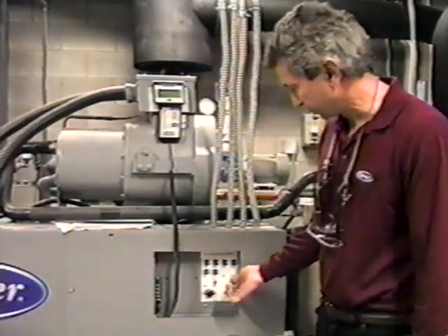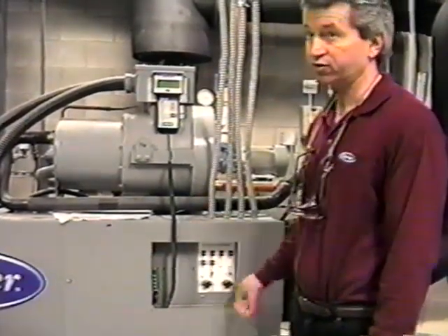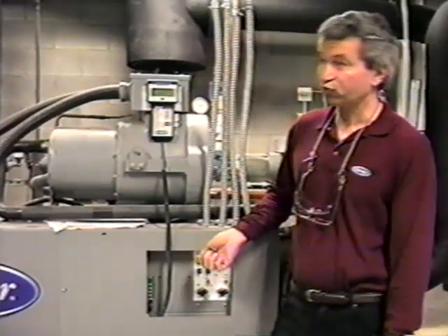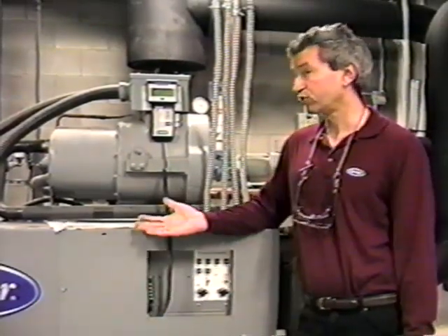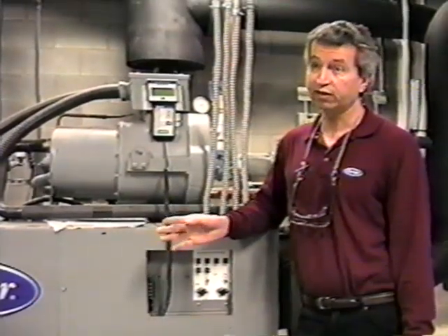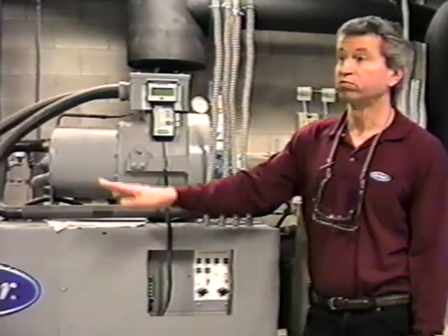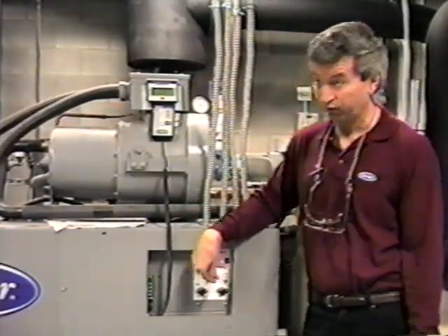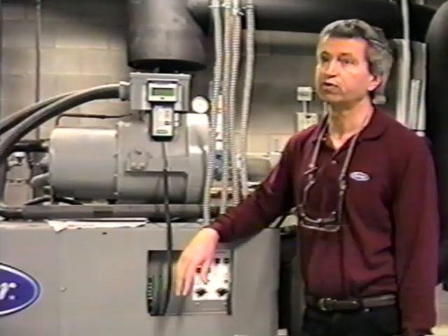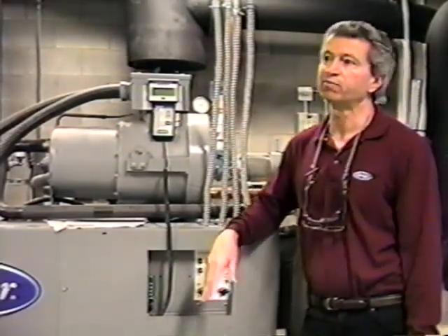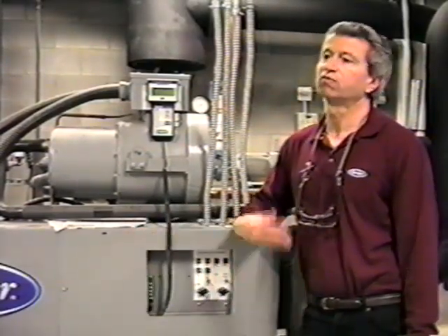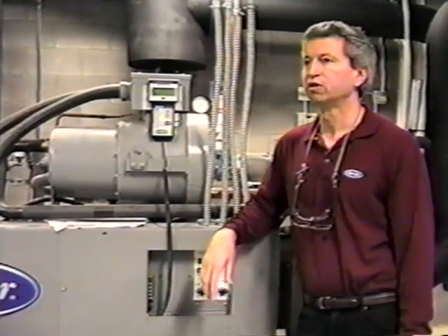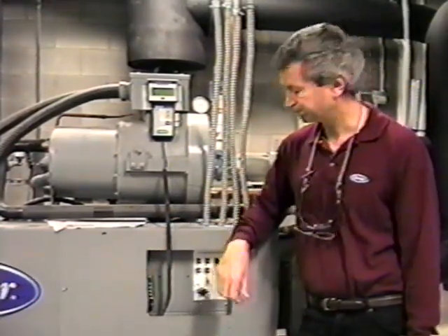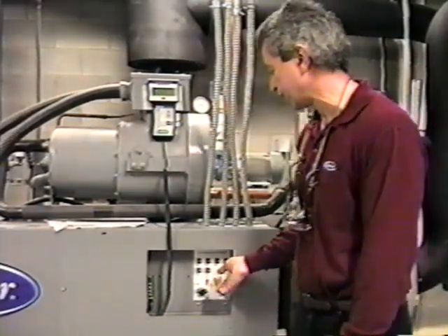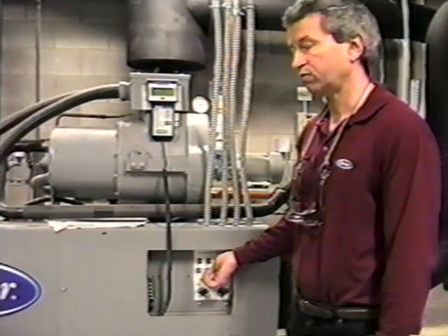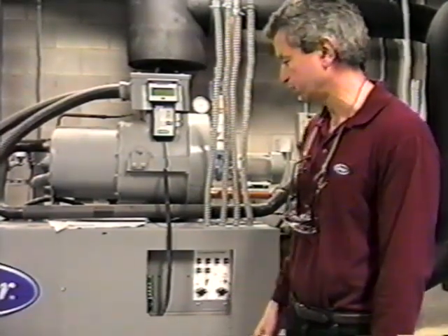The other switch you'll see here is what we call emergency, and basically that's just on or off. I don't know if you noticed, but when I turned the switch off before, it took 2-3 minutes for the machine to actually shut down. Well, if you ever need it to shut down immediately, you can just hit that to off, and boom, everything will just drop out, because essentially what that does is it interrupts control power to the processor, or the brains portion of the control system. So it'll just drop out immediately. Will it hurt anything? No. It just won't allow it to go through its normal pump down mode, which is part of its normal cycle. So that should always be on, and then this is your operating switch. Again, either remote contact or off mode should be the position of that switch.